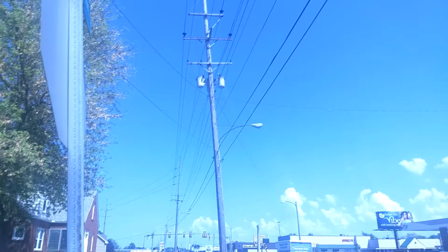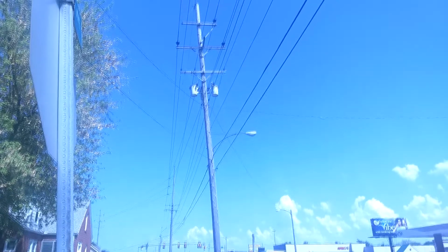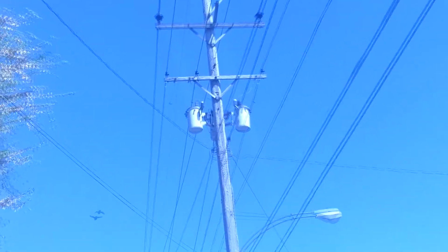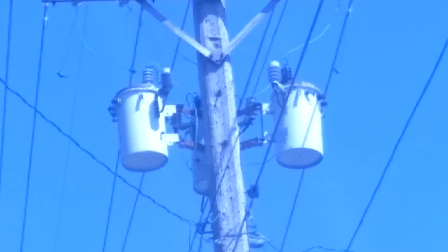The set of wires at the top of these poles is at 69 kV. They can be seen going left towards a small substation. The lower set of wires connect to pole-mounted transformers that reduce the 13.8 kV down to 480, 240, and 120 volt, which then connects to businesses and houses. A transformer is just an iron core inductor with multiple windings.